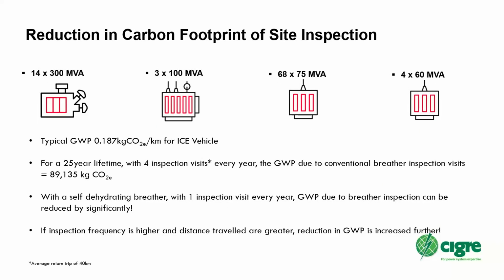We also calculated the reduction in carbon footprint for site inspection. For this site, we used a value of 0.187 kg CO2 equivalent per kilometer for a petrol vehicle, roughly for a 2000 cc petrol vehicle. We calculated the distance traveled each time to reach the transformers, which varied, but averaged around 40 kilometers per return trip. Based on that, over 25 years, just for breather maintenance, the life cycle carbon footprint adds up to around 89 tons.